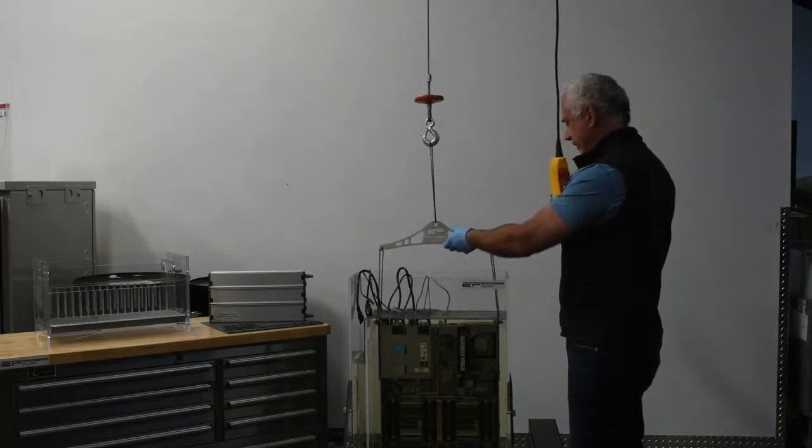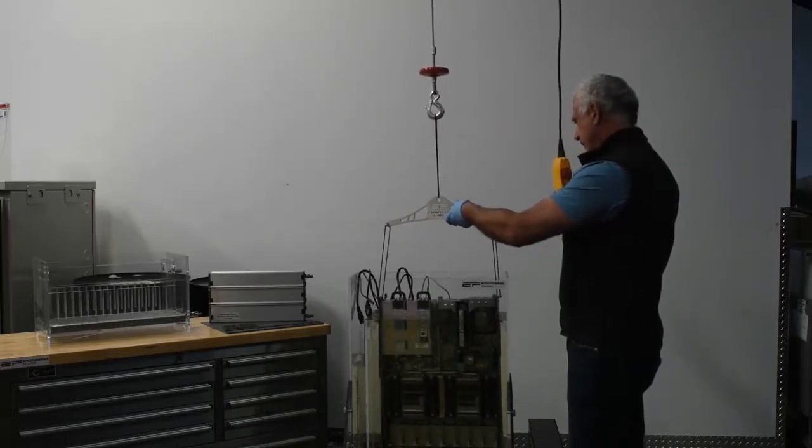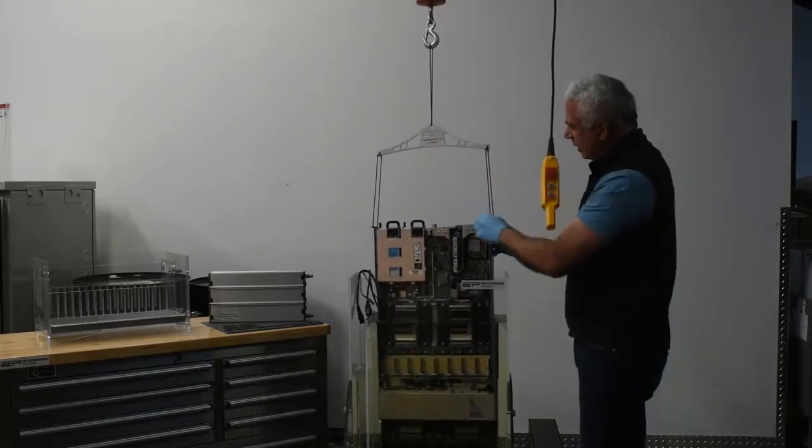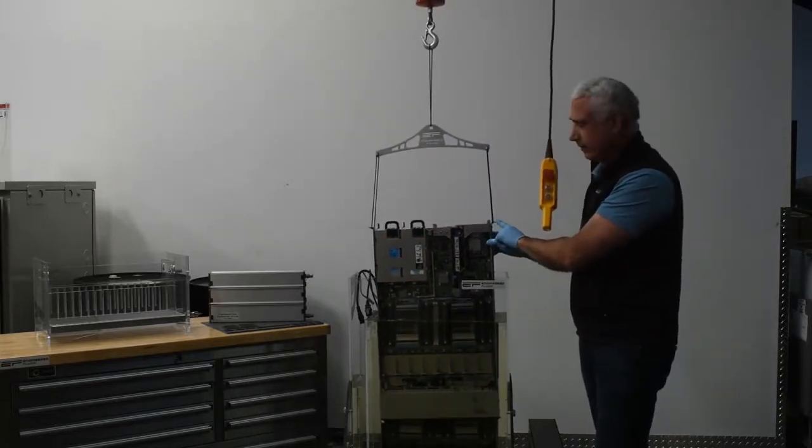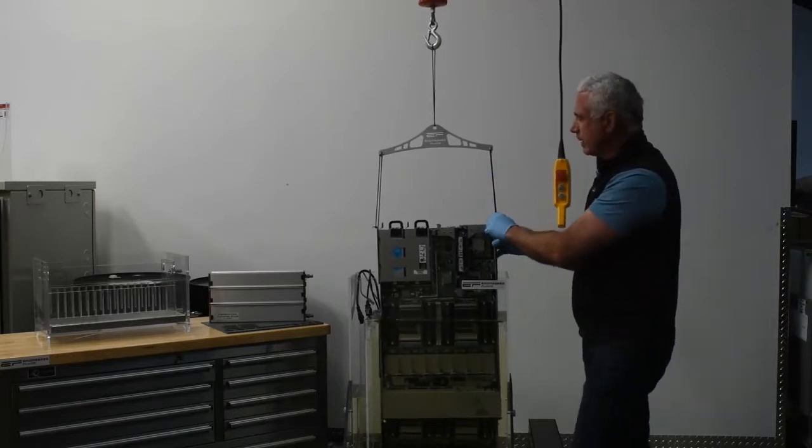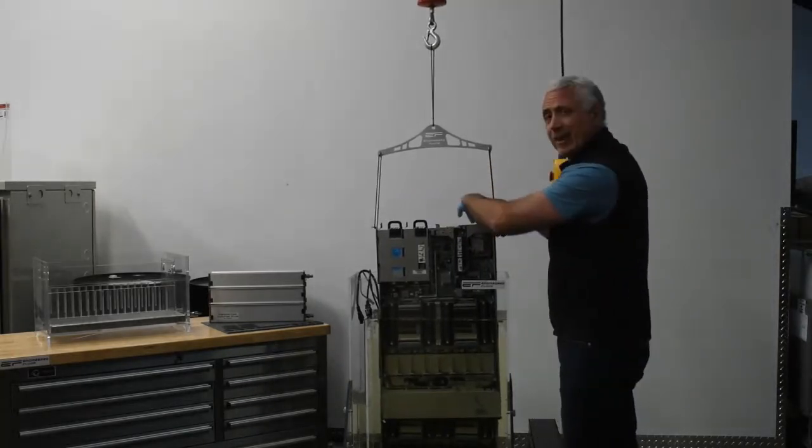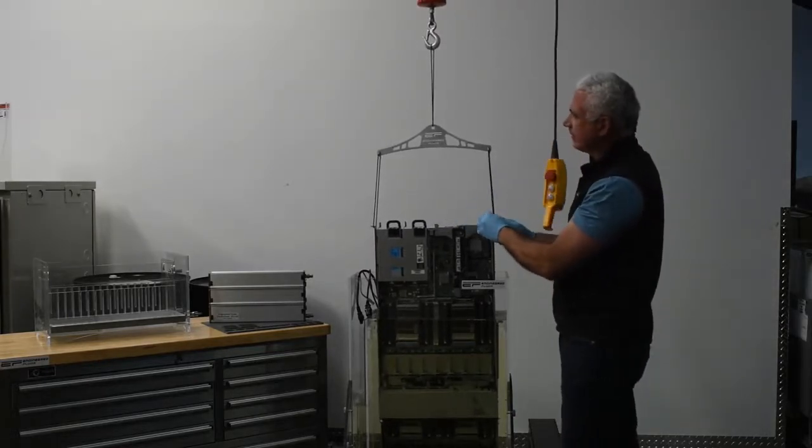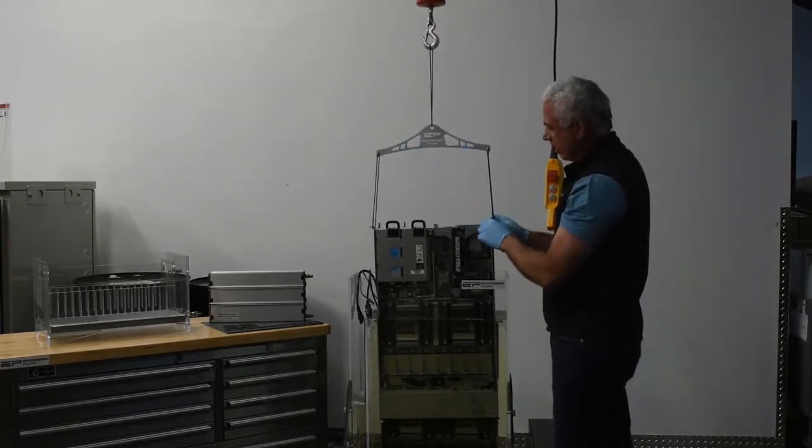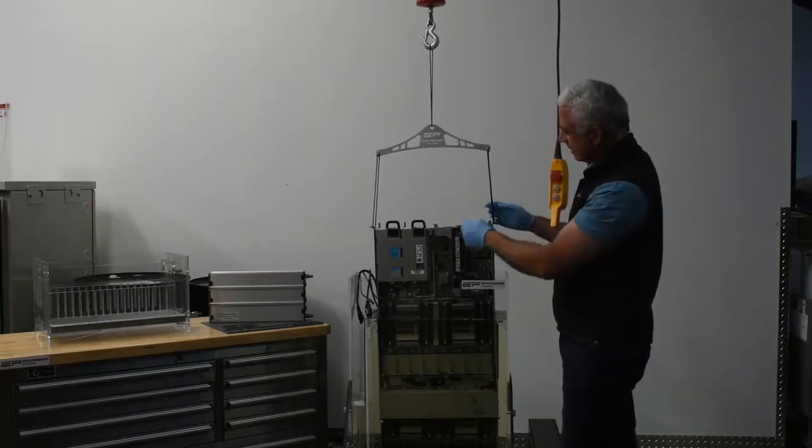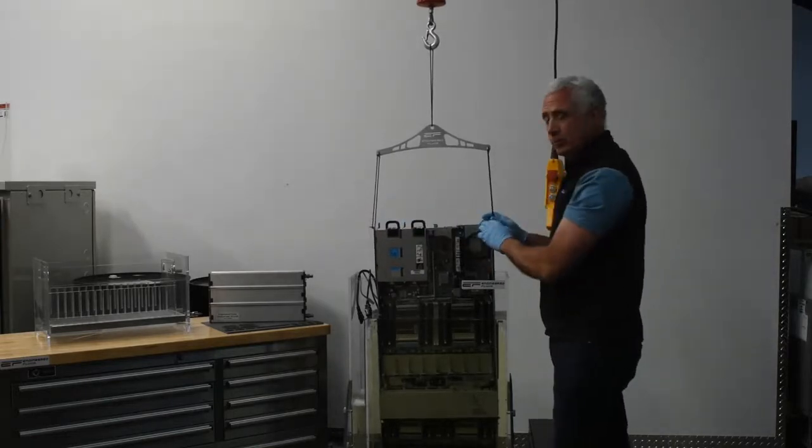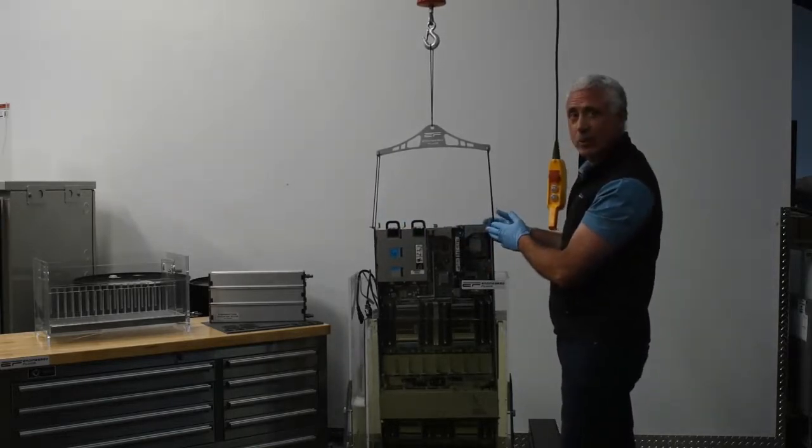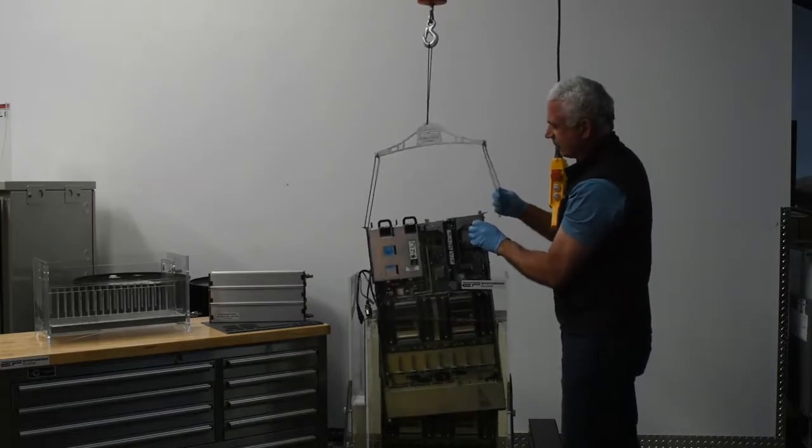So I'm going to bring this server here up and you can see it's going to go ahead and lift it straight up. And I'm going to show you all of the servers have an ear here. So you can do a lot of complicated things. We've seen people that have put brackets on the back. Our favorite is that we make these lifting arms. They're slightly narrower than the server and because of that the tension on these two wire loops is basically pinched together by the weight of the server.